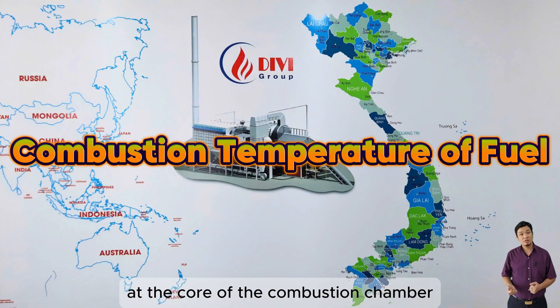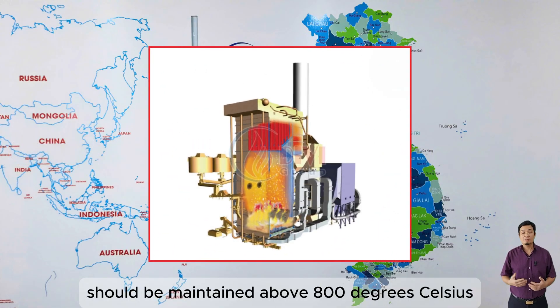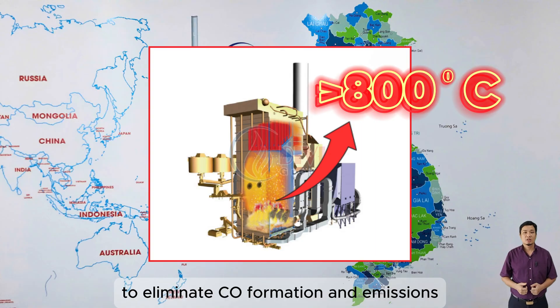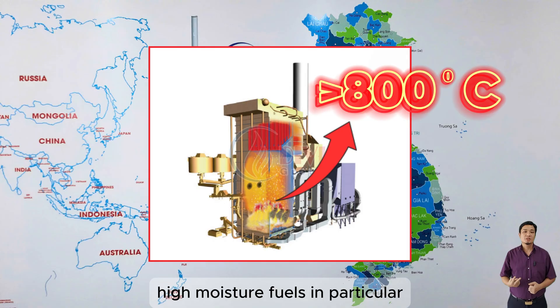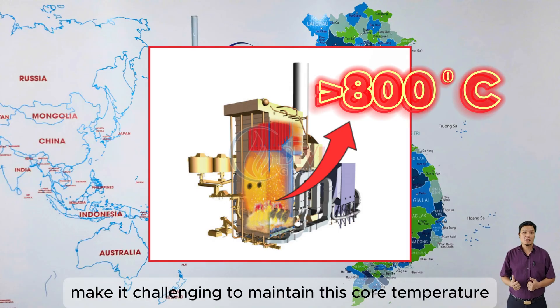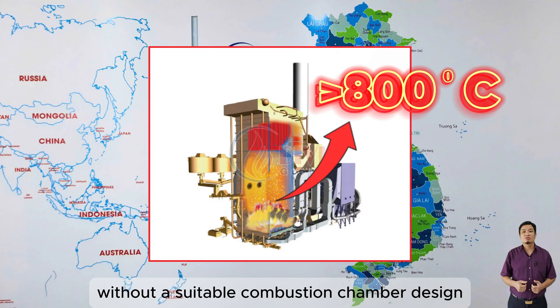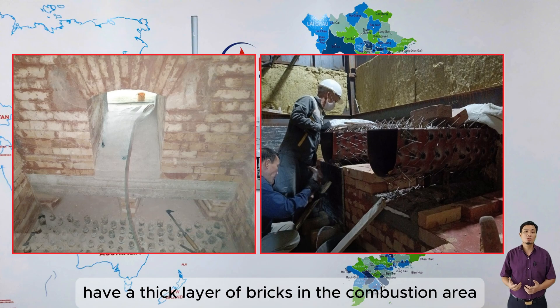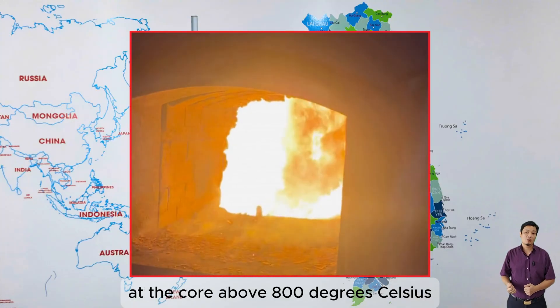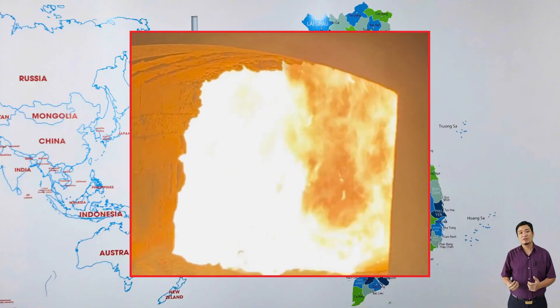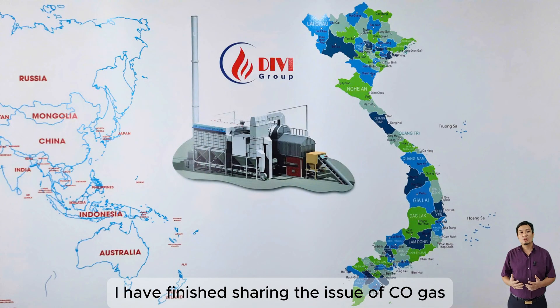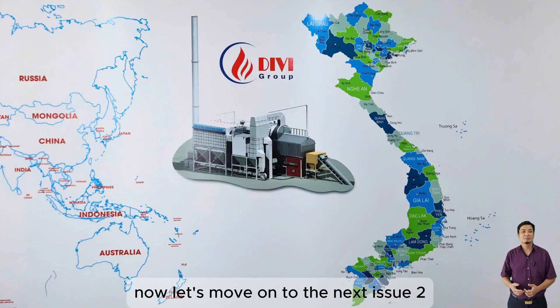Fourth, combustion temperature of fuel. The combustion temperature at the core of the combustion chamber should be maintained above 800 degrees Celsius to eliminate CO formation. High moisture fuels make it challenging to maintain this core temperature without a suitable combustion chamber design. This is why DIVI Group's boilers have a thick layer of bricks in the combustion area, creating a fuel kiln that intensifies combustion at the core above 800 degrees Celsius. Proper design ensures optimal combustion temperature. That concludes the issue of CO gas.